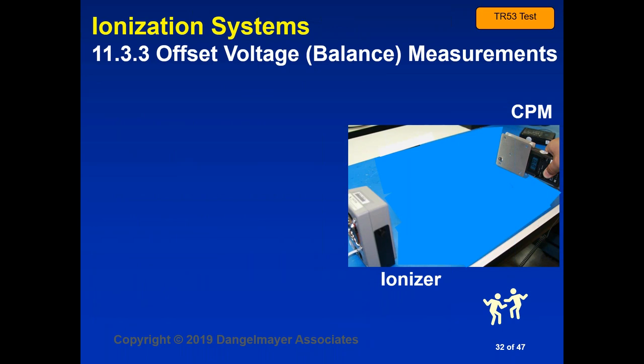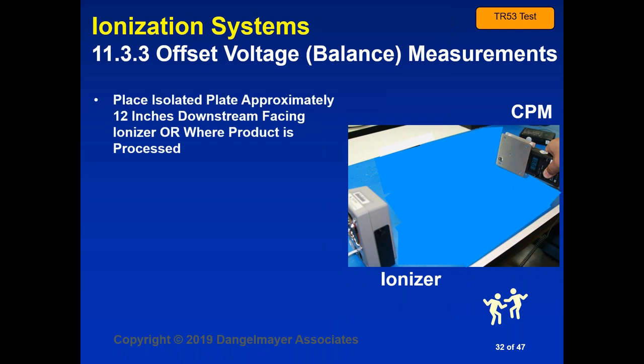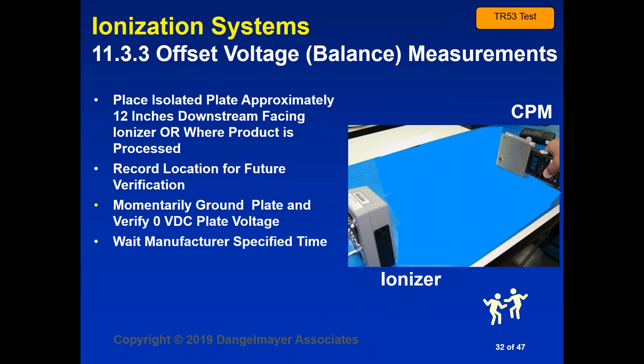The setup for making your offset or voltage balance measurements is very similar. The difference here is only that you don't have the timer, same instrument. Again, you place the isolated plate assembly 12 inches downstream facing the ionizer or where the product is processed. Remember that location. You're going to record that location for future verification so that you make measurements in the same place, which is the critical part of your process.